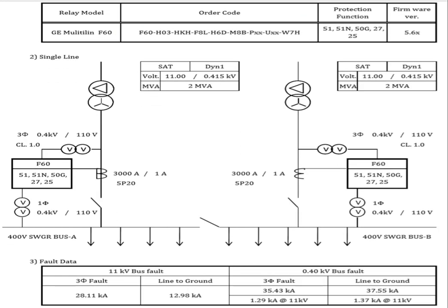Next. As I mentioned earlier, our subject relay is the GE Multilin F60 feeder management relay. This has the following functions. We have here relay 51, 51N and 50G, 27, and relay 25. We will not be using relay 50 for this discussion, and this will be disabled as well. Okay, so these relays are in the following incomers, for bus A and bus B.